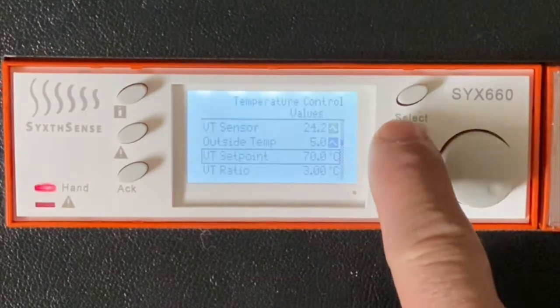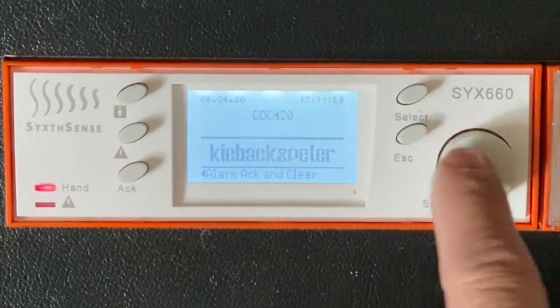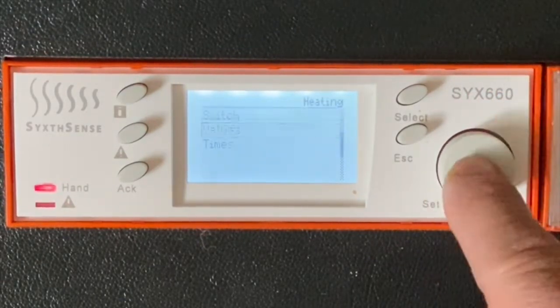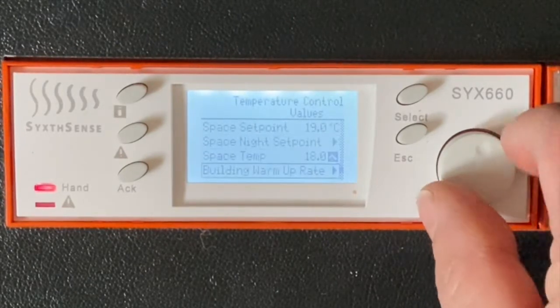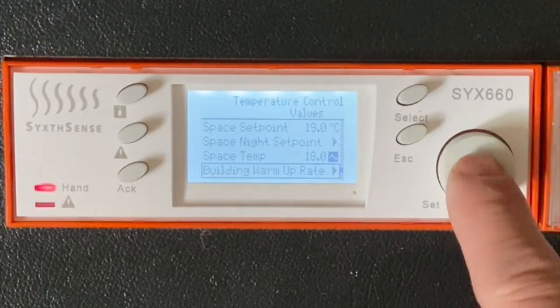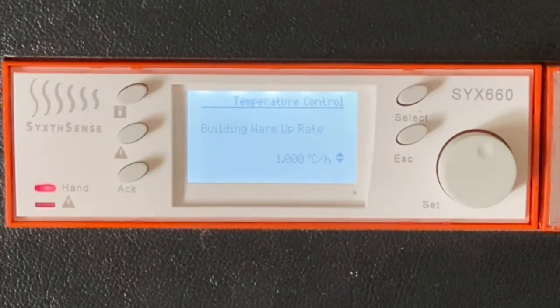One other setting I just want to point out is the warming up rate of the heating system. So to get to that, we choose the switch, we choose heating, we choose values, we choose temperature control, and we just scroll down and we choose the building warm up rate. Hit the wheel on that, and you can see on this particular controller it's been set to 1, probably from a previous video that we've been preparing on this particular product. And this is where we set the building warm-up rate, and we can adjust that, and we can make the necessary changes to clear the building warm-up alarm, optimiser low limit alarm that we've discussed in a separate video. But this is where you can make the same change for the same reasons, and remove the alarm from the system as necessary.